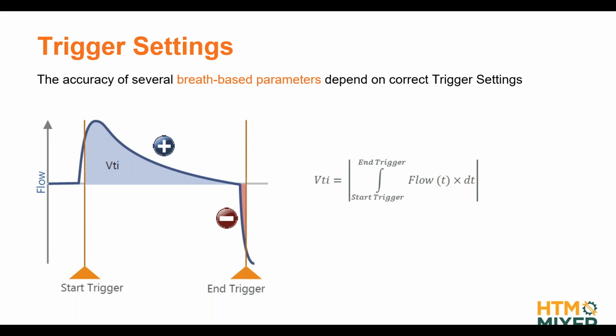If, like in this example, our triggers are a little bit delayed in time, then this has an effect on the accuracy, for example on the VTI calculation. Because mathematically, what the device is doing is, when the start trigger hits, it starts integrating, meaning summing up the flow that runs through the device, until it's stopped with the end trigger, so that the inspiration time is over. And in this example, because the trigger settings are not that close to reality, we're going to miss a part for our VTI calculation. And then even worse, because here our flow goes negative, we count a part of the exhalation in our inspiration volume calculation. This is going to be counted negative. So in this specific case, our measured VTI is going to be significantly lower than reality. Okay, so we want to make sure that we have as accurate triggering as possible.